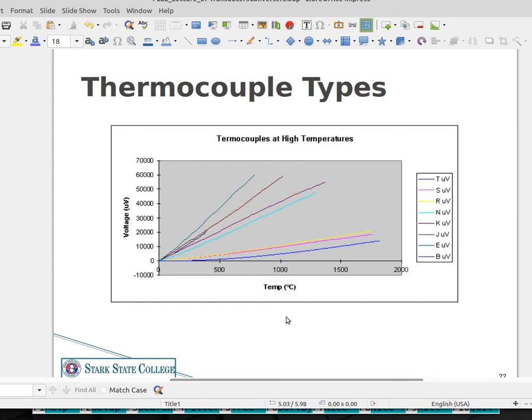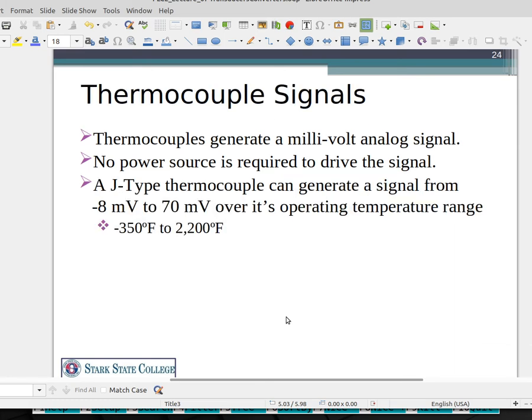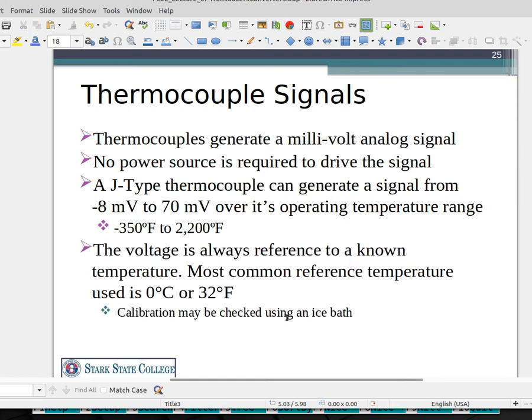You can't just do a simple scaling equation and make a nice linear line to determine the temperature. Thermocouples, like piezoelectrics, generate a very small voltage in the millivolt range, and again you don't need a power source — they're passive devices. The range is from about minus 8 millivolts to 70 millivolts for that large temperature range.